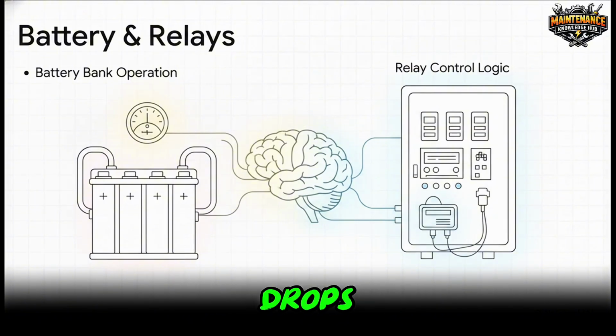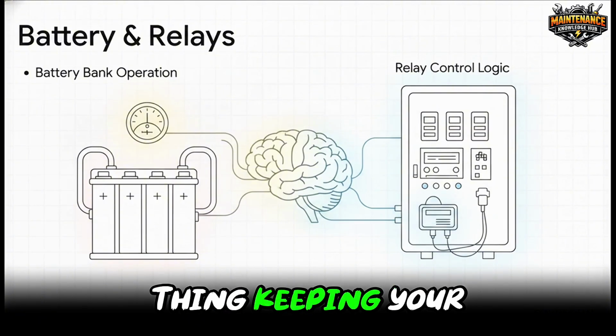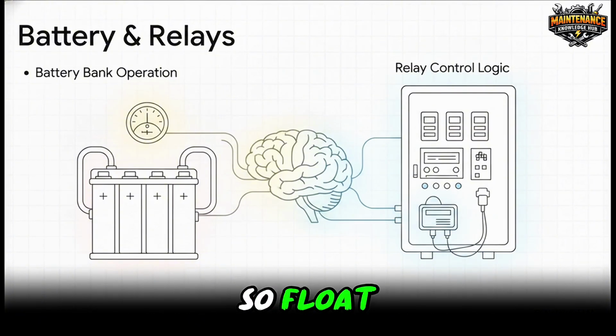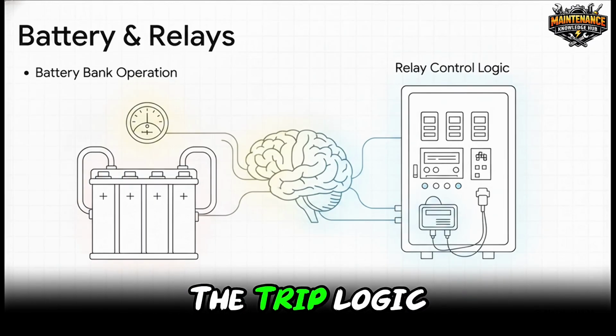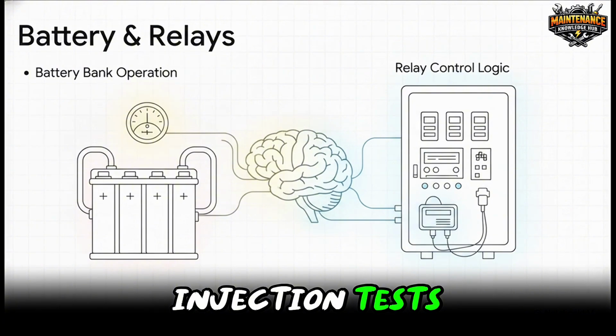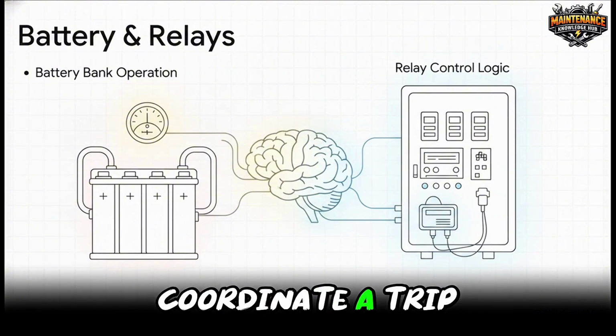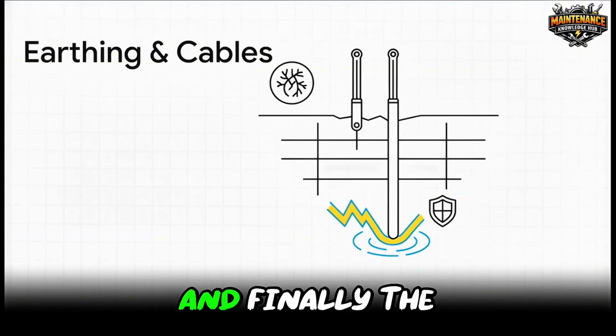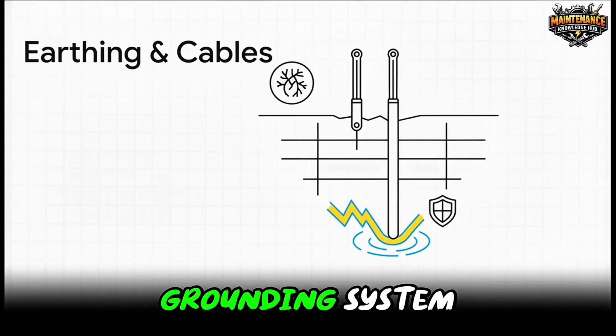If the grid drops, that battery bank is the only thing keeping your protection logic alive. So float voltage and specific gravity checks are just vital. And for the relays, we verify the trip logic and run secondary injection tests to guarantee they're going to flawlessly coordinate a trip when the system goes critical. And finally, the arteries and the grounding system.